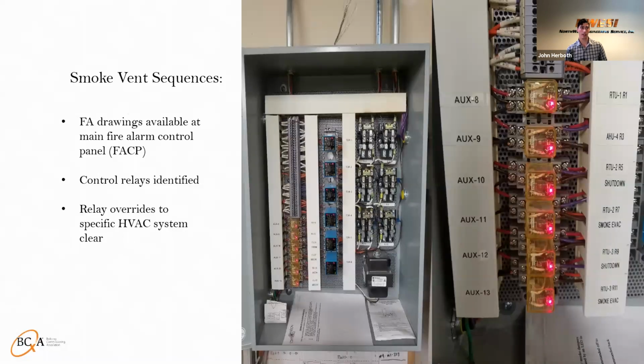And then you're going to get lucky sometimes in the field with smoke vent sequences that are easy to identify, with inputs and outputs for what systems they shut down. This is definitely the ideal case, like on that right picture, where you could easily, with a little direction, operate the fire alarm panel and put everything in the right mode of operation to confirm it.